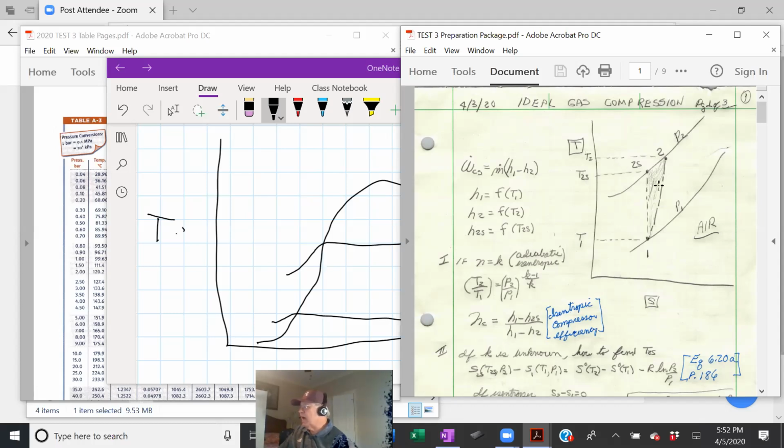So our compressor gets hot due to the friction and other losses inside the compressor. It creates heat. That heat goes to the shell of the compressor, and it's eventually convected away. Or the way we did our compressors at Eaton, they were so big and high performance that we couldn't depend on atmospheric air to cool them and take this parasitic heat transfer away. So we actually used cooling water inside the compressor itself, and this heat of compression was carried away by the cooling water.